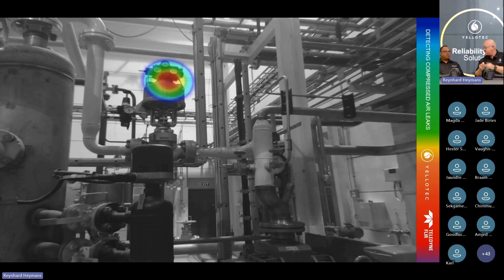Manifolds again, pneumatics, ammonia compressors, argon compressors, oxygen. Even oxygen. In hospitals, all of that oxygen line is coming from a compressor that we need to monitor as well. When we start talking about the difference between, will I be able to pick up a gas leak?